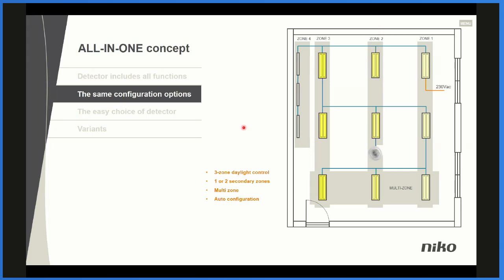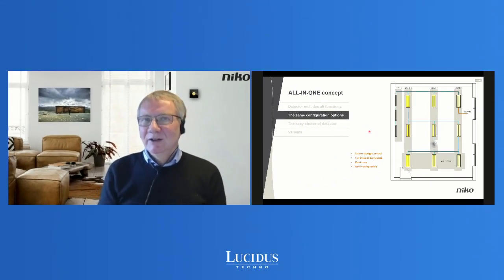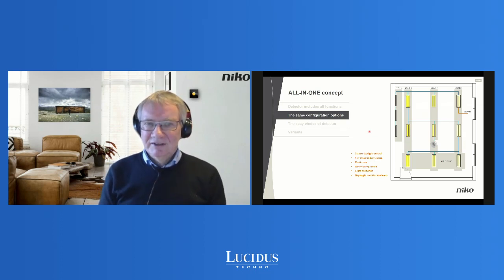Sometimes we do discover that a luminaire is broken and we have to replace it. For that, we have built in an auto-configuration functionality. That means if a luminaire has to be replaced, you just replace it, one at a time, and it will automatically gain the configuration of the broken one. It will automatically be transferred into the replacement luminaire. That means the maintenance part is very, very easy to do. Different light scenarios and also day and night functionality, I'll get back to some of these a little bit later.